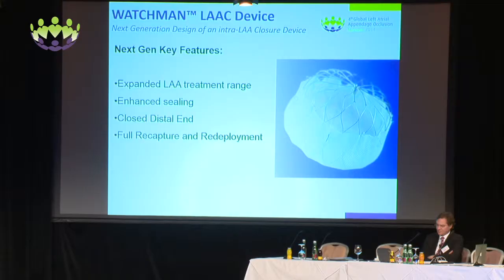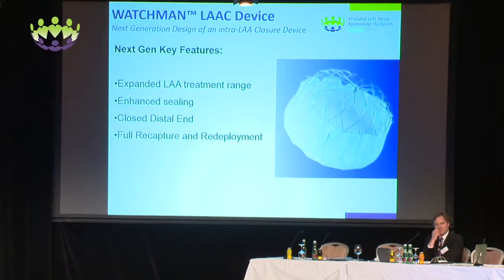Concerning the Watchman, the next generation will expand the LAA treatment range, so we will be able to close larger appendages. As you know, the largest Watchman device is now 31 millimeters. Then there is a better sealing membrane to try to seal the appendage, and a closed distal end to try to prevent perforation that sometimes occurs with the distal part of the device that we put far in the appendage. The ability to fully recapture and redeploy the device in place should be available very soon, let's say in a year.